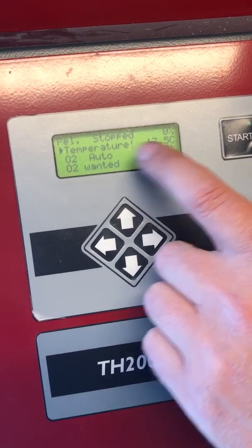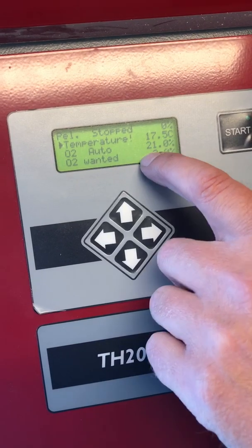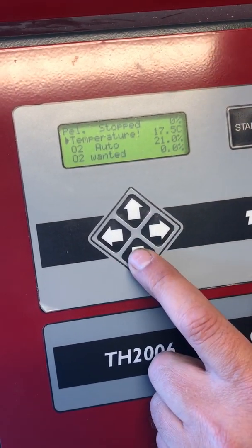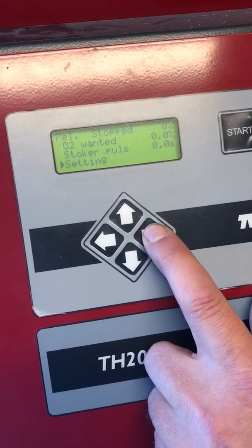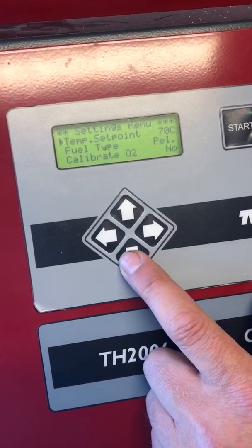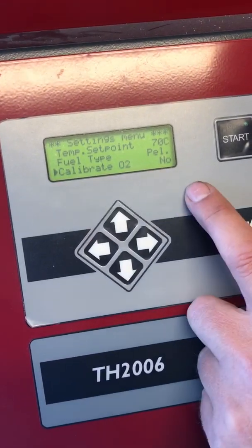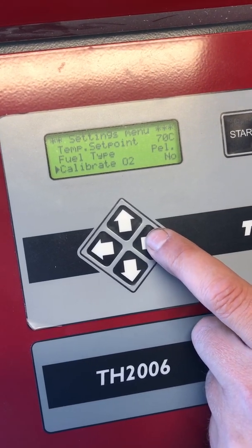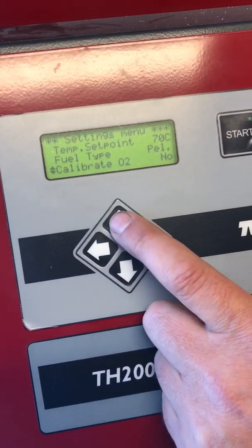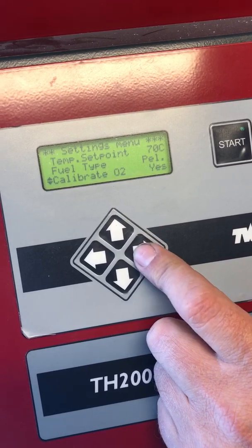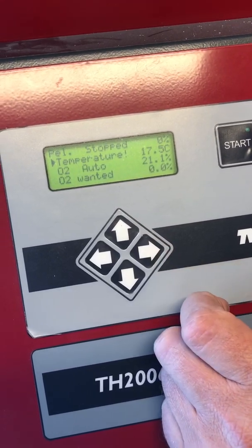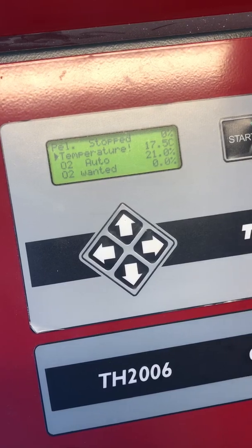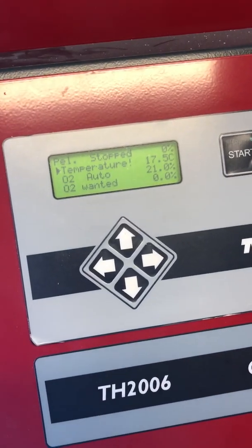If it doesn't show close to 20.9, we have to calibrate the lambda probe. We go down to settings and down to calibrate O2, and we just change this one from no — you can see the arrow changing — press up to yes. Then it jumps back to the front page, and then it shows 20.9 or 21.